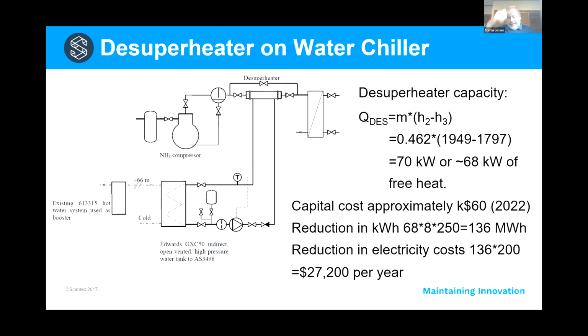Now, in calculation terms, if we know the mass flow of refrigerant, this is what is called M in that equation, and we know the enthalpy differences, this is from the previous picture, we can estimate here that we can recover about 70 kilowatts maximum out of this desuperheater. So I reduced that by 2 kilowatts for a couple of reasons. First of all, the pump costs a bit of power, and also the desuperheater has a pressure drop. And when we cause a pressure drop in the discharge line of the compressor, we increase the power on the refrigeration compressor marginally. So these couple of kilowatts account for those losses.